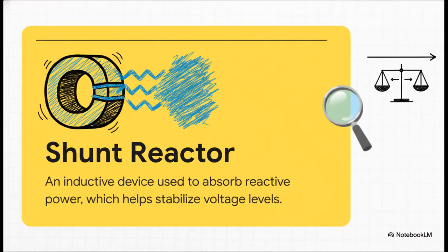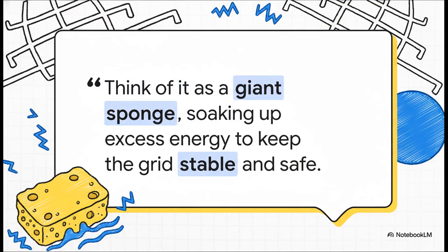A shunt reactor is basically just a giant coil. It's an inductive device, and its entire purpose is to be the complete opposite of that capacitive effect we were just talking about. It's designed to absorb that problematic reactive power, acting like a perfect counterbalance to pull voltage levels back down to normal. The best way to think about it is like this: a shunt reactor is like a giant electrical sponge. It just sits there connected to the power line, and its whole job is to soak up all that extra jittery energy before it can cause any trouble. It's simple, it's effective, and it is absolutely essential.